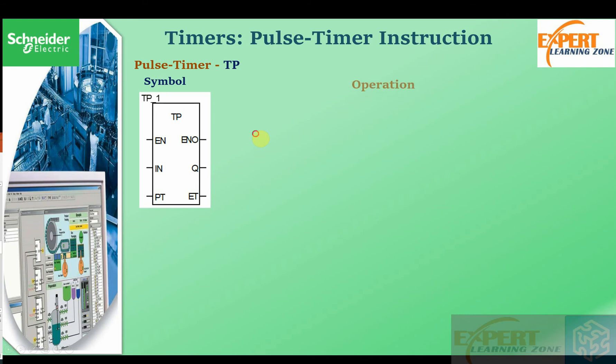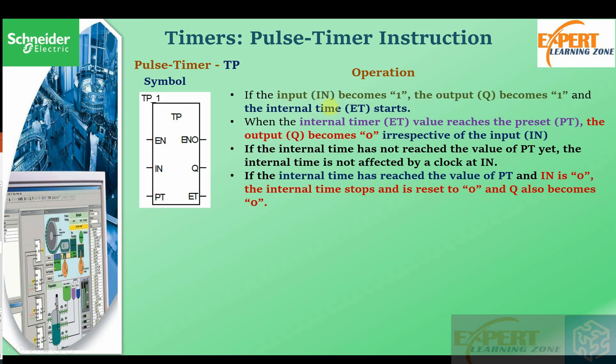The text says: if the input IN becomes one, the output Q becomes one and the internal time ET starts. When the internal time ET value reaches the preset value, the output Q becomes zero, irrespective of the input IN. If the internal timer has not reached the preset value yet, the internal time is not affected by a clock on the input pin. If the internal time has reached the preset value and IN is zero, the internal time stops and resets to zero, and Q becomes zero as well.